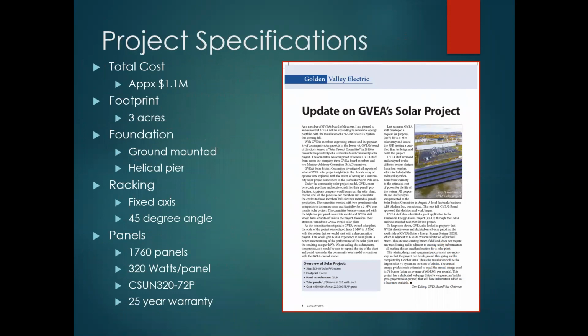So the total cost is coming in at just over 1 million, 1.1 million, for 3 acres in size. The foundation will be a helical pier foundation type. We are going with fixed axis, so no tracking, fixed at a 45-degree angle. The total size is close to 1,800 panels at 320 watts a panel, coming out to about 560 kW DC, with the panels carrying a 25-year warranty.